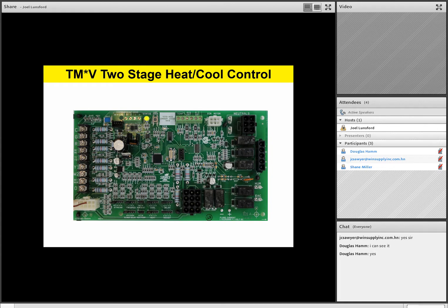Again, this board is going to be found in our variable speed, two-stage variable speed gas furnaces. They're a great furnace, been very reliable. This board is also communicating capable, so if you have a situation where you have a fully communicating system, this happens to be a control board that you can go either 24 volt or communicating. And because it is a variable speed ECM motor, instead of having physical speed taps that we're going to have to take down to the motor like our previous boards, this one we're going to have some airflow adjustment jumpers on the board itself. So the big thing about the variable speed is that you'll set up your airflow via jumpers on the board compared to actual speed taps on the motor.